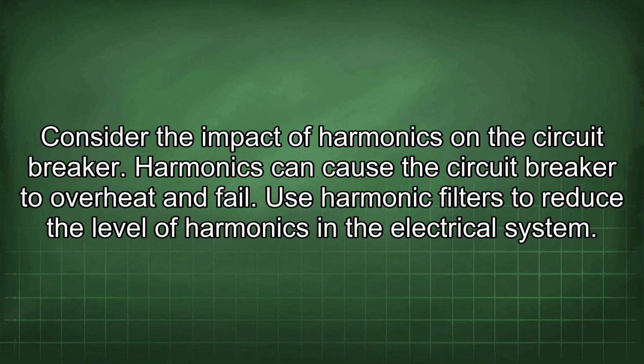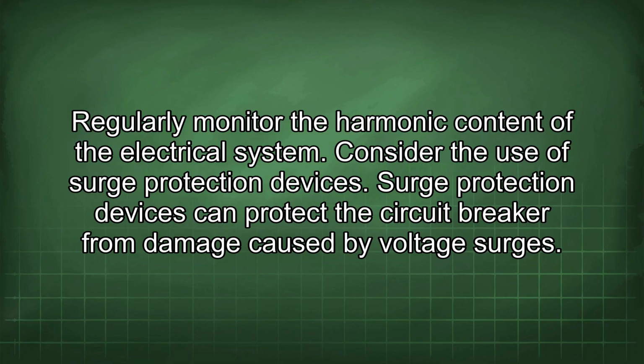Consider the impact of harmonics on the circuit breaker. Harmonics can cause the circuit breaker to overheat and fail. Use harmonic filters to reduce the level of harmonics in the electrical system. Regularly monitor the harmonic content of the electrical system.